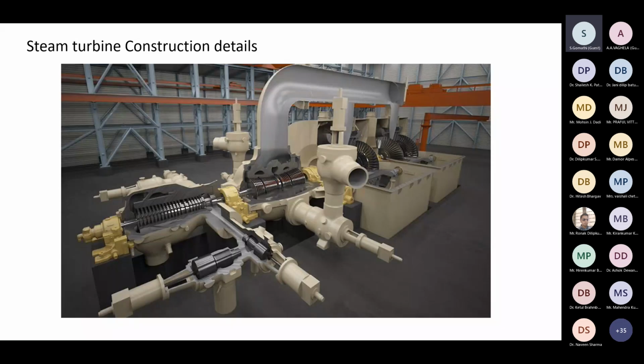Before going into that impact, let me explain the construction details of the steam turbine. This is a steam turbine, typically a 660 megawatt supercritical steam turbine looks like this. Also 800 megawatt units - we have about four 800 megawatt machines already installed, or more. One is in our Gujarat also, in Wanakbori near Dahod. There also we have one big 800 megawatt machine installed and generating electricity.